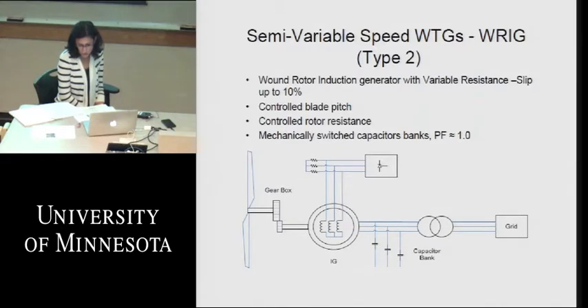And again, it's just a wound rotor induction generator, instead of using rotor bars like a squirrel cage design, so we also need a capacitor bank on there that will bring us back to a power factor around 1, so that we're benign to the utility that we're connecting to. We're not overexciting and causing high or low voltages on their system as power goes in and out and the inductive draw on the generator changes. We just offset whatever induction requirement of the generator with the capacitor bank, and we're pretty good with that.